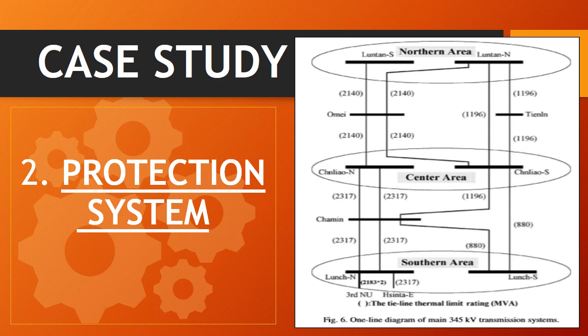For protecting the 345 kilovolt transmission systems, we simulate distance relays and overcurrent relays on every 345 kilovolt tie line between areas. The distance relay protective zones are set to be 92, 150 and 220% of the line impedance for zones 1, 2, 3, whose pickup times are 1.5, 10 and 60 cycles respectively. All opening times of circuit breakers are 1.5 cycles and reclose time is 36 cycles. The operating currents of overcurrent relays are set to be 1.5 times the line terminal rating and relay time is around 0.6 seconds.